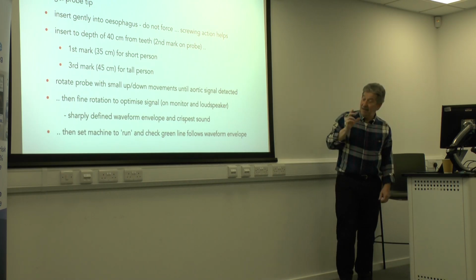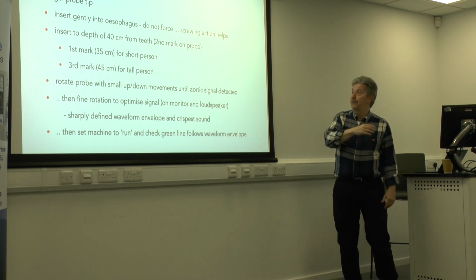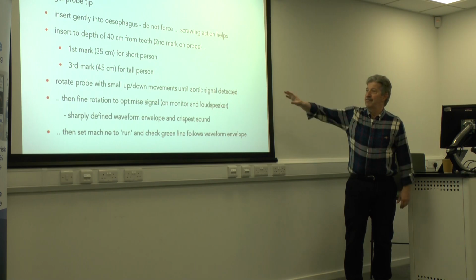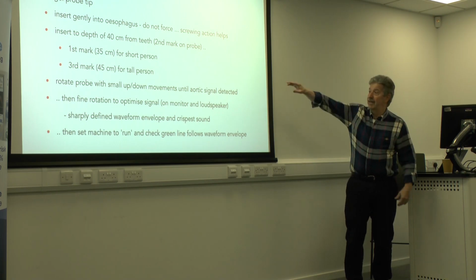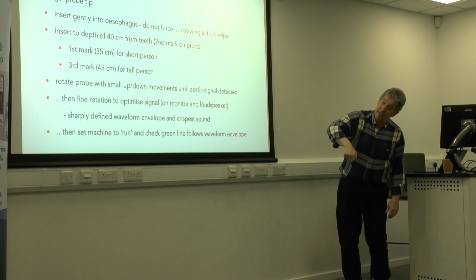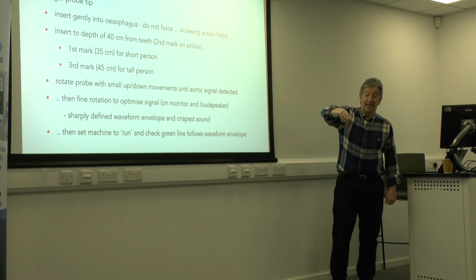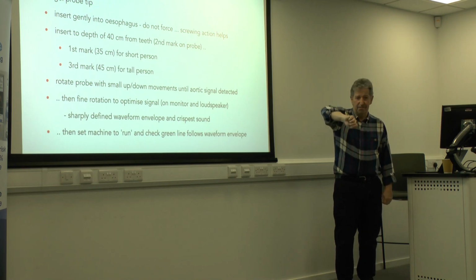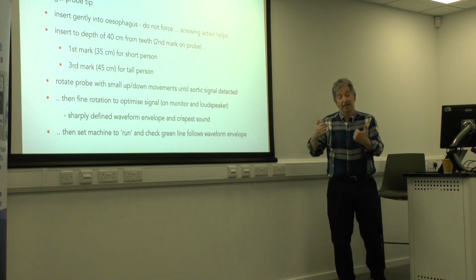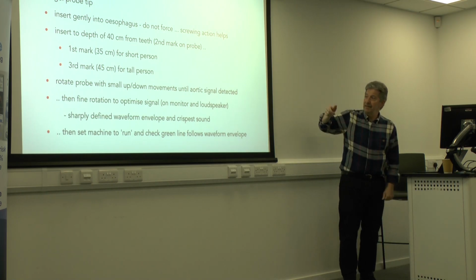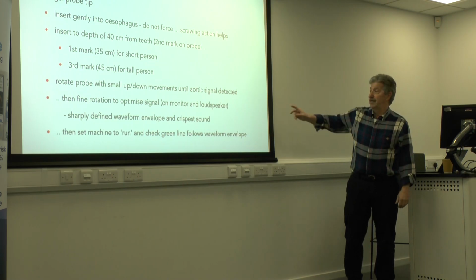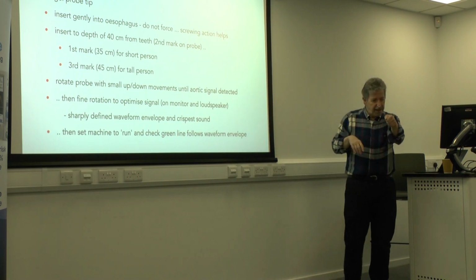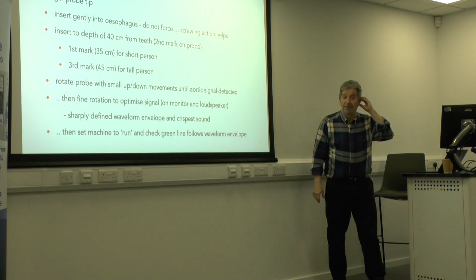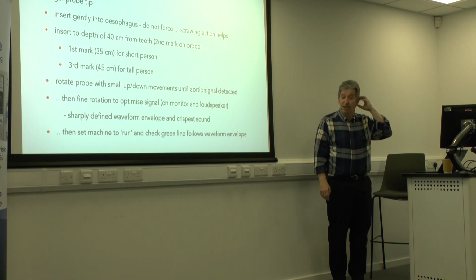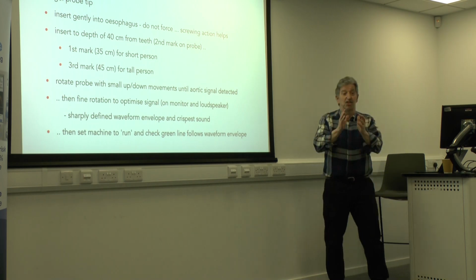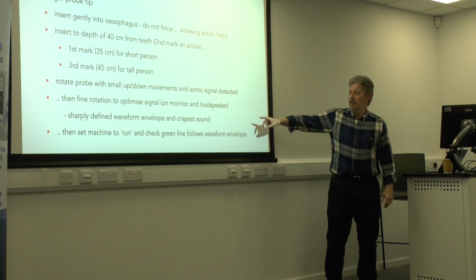As I mentioned before, there are 3 marks on the probe: 35, 40, 45 centimeters from the teeth. So for your average person, it's around the 40 mark. You might need to come up a bit if they're short and go in a bit further if they're tall. But basically, you get it to that approximate depth and then move up and down and side to side, because if you remember the aorta is behind the esophagus, until it's focused on the aorta. I'll show you some signals there. So basically, you tweak it until you get a combination of both the best sound you can get, so the highest pitch on the loudspeaker, and the sharpest signal you can see on the monitor. And I'll show you that in a sec.